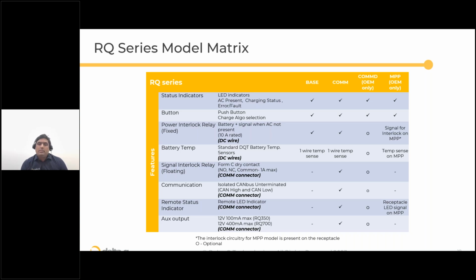For the MPP, we have the signal for interlock on MPP, the temperature sensor, and the receptacle LED signal on the MPP. The customer can choose which variant of the four is suitable for their requirements, and based on that, select the particular charger.